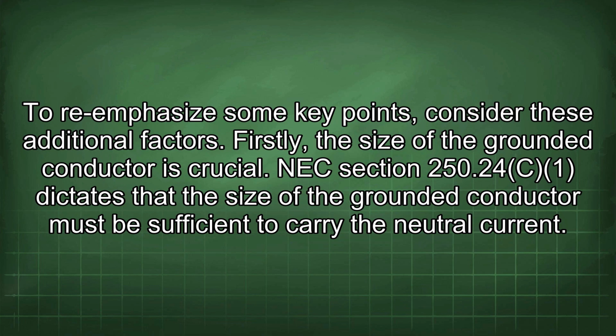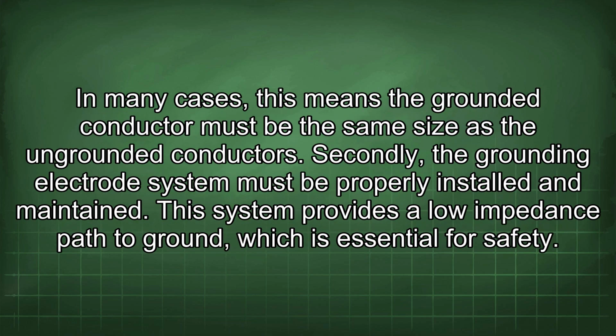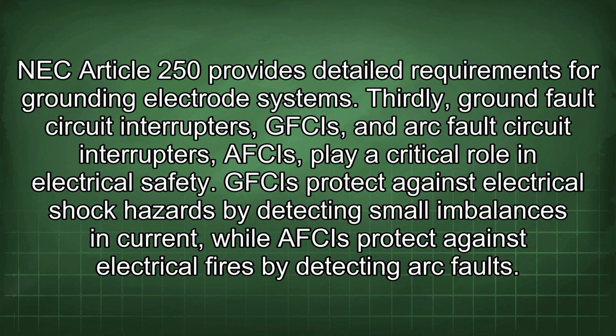Firstly, the size of the grounded conductor is crucial. NEC Section 250.24 dictates that the size of the grounded conductor must be sufficient to carry the neutral current. In many cases, this means the grounded conductor must be the same size as the ungrounded conductors. Secondly, the grounding electrode system must be properly installed and maintained. This system provides a low impedance path to ground, which is essential for safety. NEC Article 250 provides detailed requirements for grounding electrode systems.